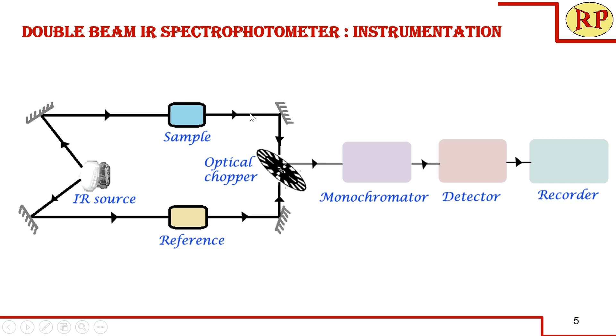The light coming out of the sample and the reference enters the optical chopper, which is a motor-driven rotating disc. There are white and black portions on this chopper — the white portions are open parts where light can pass through, while the black portions reflect the light instead of transmitting it. When rotating, when the light from the sample hits the white portion, the light from the reference will hit the black portion. That is, when the sample beam is transmitted, the reference beam is reflected, and vice versa. This way, the optical chopper alternately focuses light from the sample and reference into the monochromator.